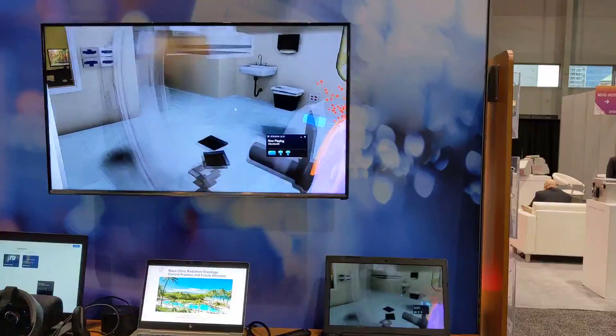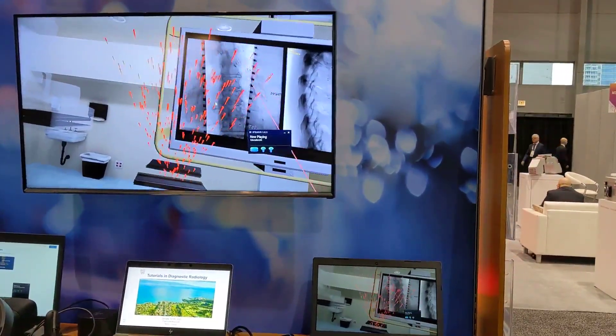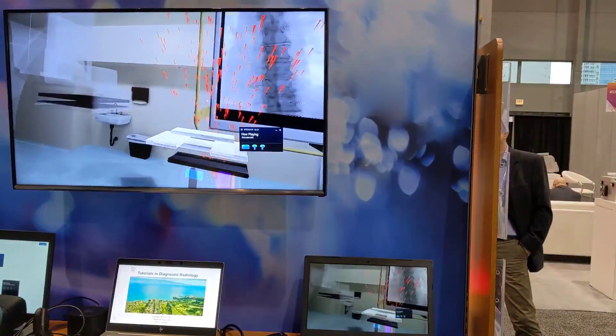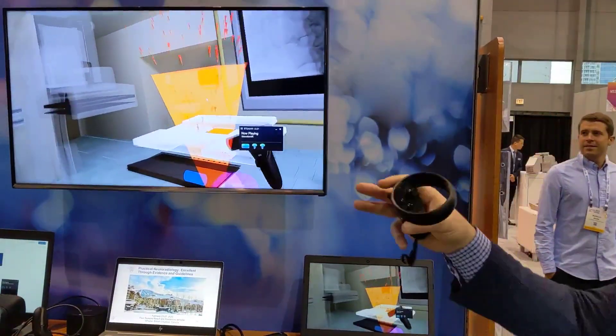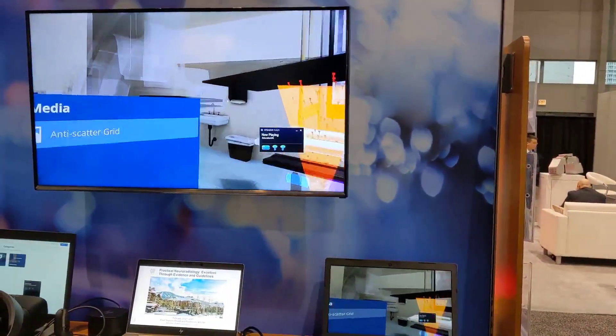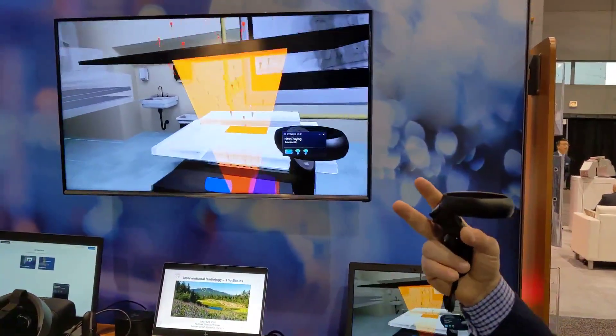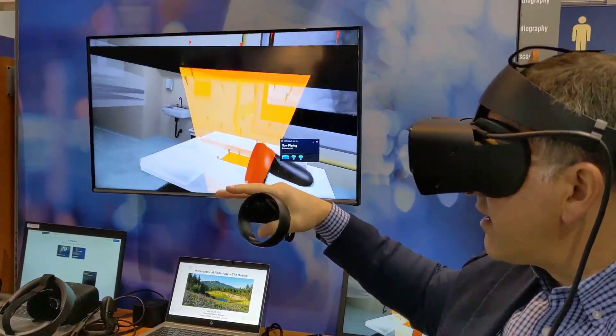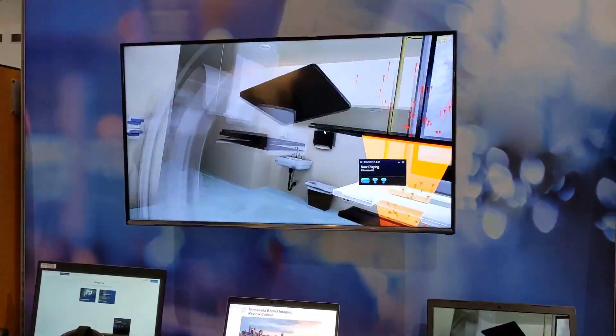We started layering in the different parts of the system. Here are the soft filters — if you look up at the monitor, you can see the soft filters homogenizing the image, which we use often in spine. Here are the hard shutters, which narrow the beam to make it smaller; these are lead that keep the x-ray beam at the size you want. Then we have an anti-scatter grid, which allows only photons going straight through to pass.